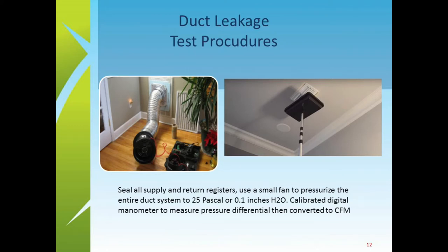That covers air sealing of homes. On ventilation — which is a whole other concept — everyone asks: you want me to seal up this home and then ventilate it? The answer is yes, because if air comes in any old which way, it's coming through an attic with debris in it and through wall spaces. The other mandatory part of the new code, when duct testing is required, uses a fan hooked up to the return system with every register in the house covered, then air is blown in at roughly 0.1 inches of water column — about what most systems are designed to run at.